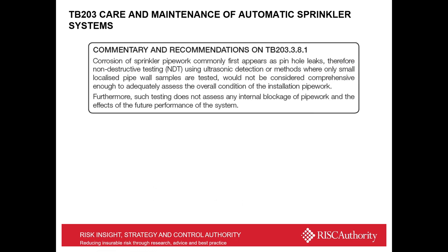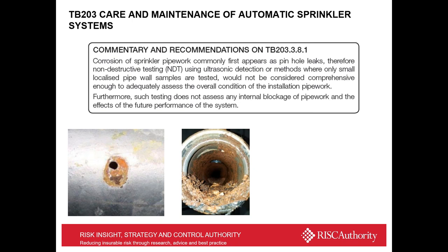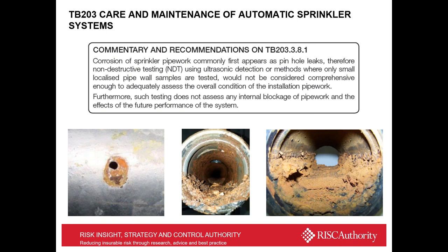We've also noted that some reports are coming through using NDT testing and also small samples of pipework are being sent away, which was not the intent of the original Annex K. So corrosion of sprinkler pipework commonly appears as pinhole leaks, as shown in the photo there. And you can see other microbial activity and sediment inside the pipework there, which leads to corrosion.